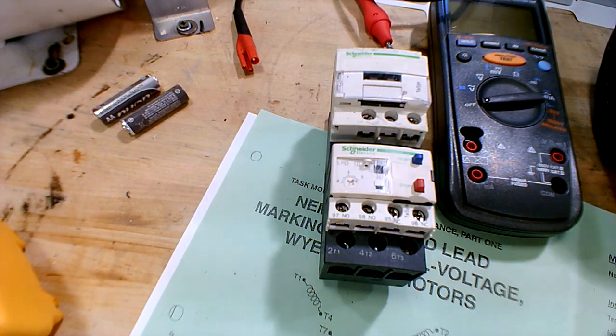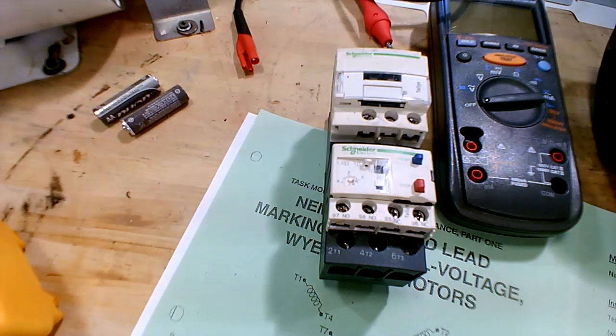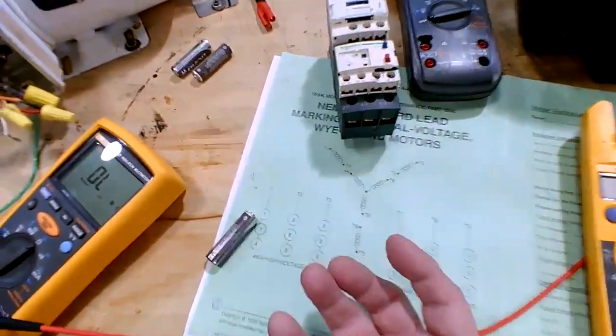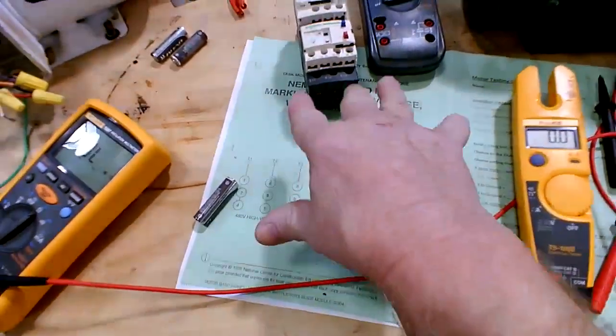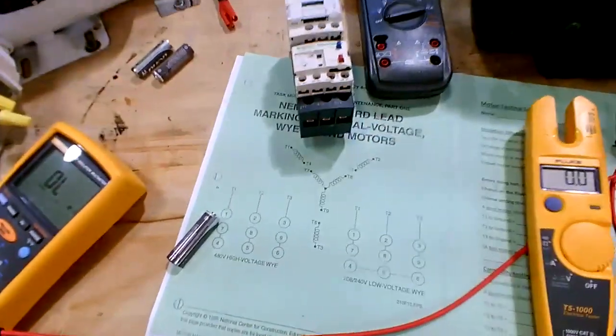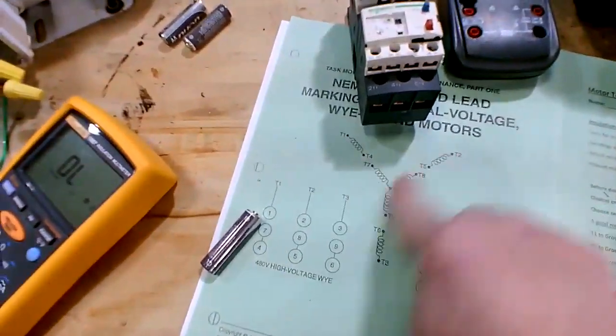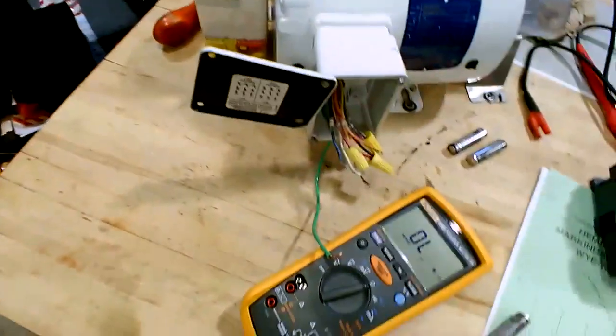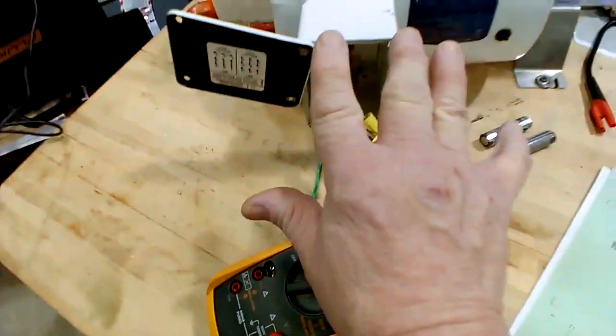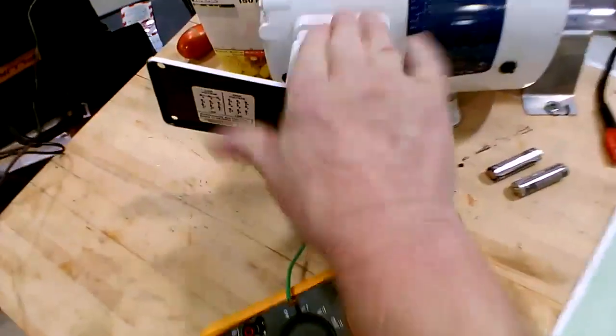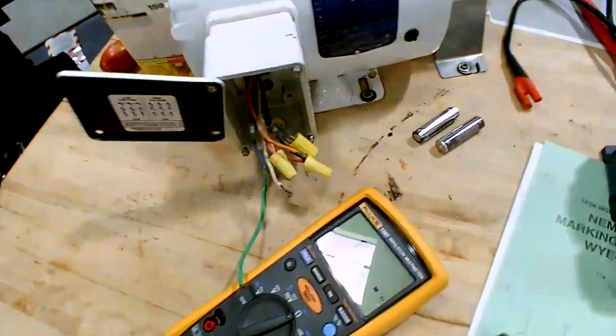When you do that resistance check that we just did, and you find out if there's something going on internally in that motor with a resistance issue, you can test from the starter out through the conduit. Take the wires off of the starter and do the resistance test through the conduit, through the wire, through the motor, and back up, through the entire run of the conduit. If you see an imbalance of resistance that way, go straight to the motor, unhook the wires, and do the same exact resistance test through the motor. If you still have an imbalance problem, it's actually in the motor. It's not the conduit. Check it.